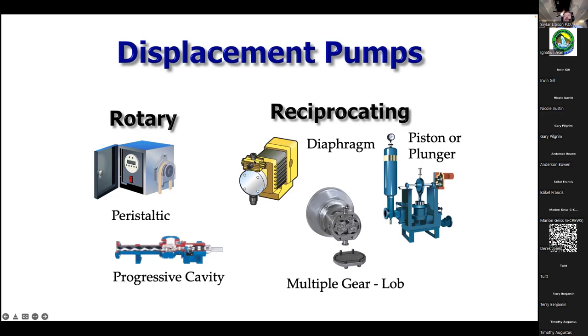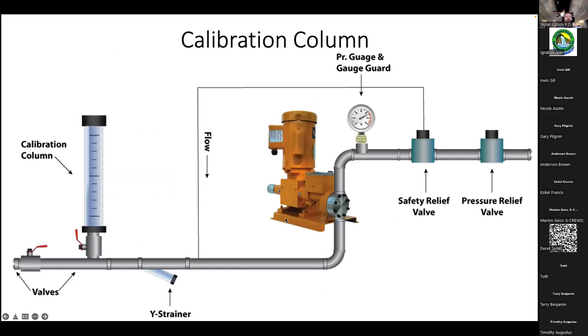Two other maintenance considerations: make sure as a PM item you clean the check valves on top and bottom of the diaphragm pump. Always ensure you understand the risks and have proper PPE on when handling any chemicals — we had an instance just last week in Georgia where an operator had chemicals splashed in their face because they did not don proper PPE. Also, how do we verify the pump is actually injecting the proper amount of chemical and working correctly?